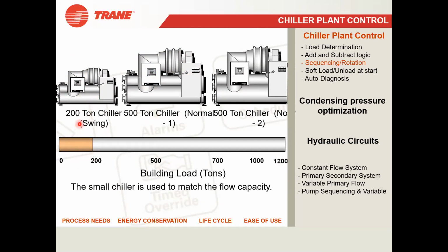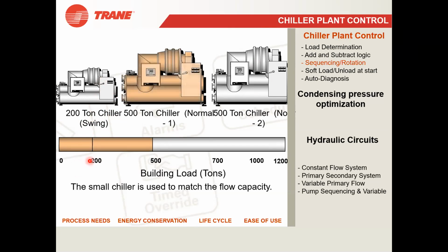Now the 200 ton chiller is running at full load, and it has reached 200 TR. You all know that a chiller gives you maximum efficiency if it is running at full load. This sequencing is done in such a way that every chiller runs at its most efficient level, that is at 100% load, or whatever cutoff load the consultant sets. Now the load is increasing, so you have to switch on another chiller. But till 500 you can manage with one chiller. When the 500 ton chiller is switched on, the 200 ton will be switched off, so that you will not have an extra electricity bill. Up till 500 TR, this one chiller will be working.